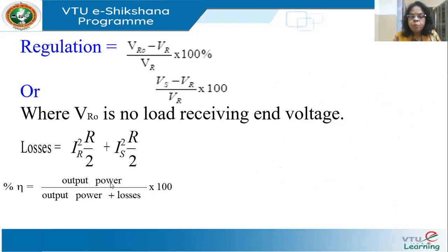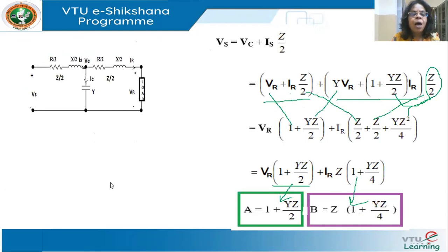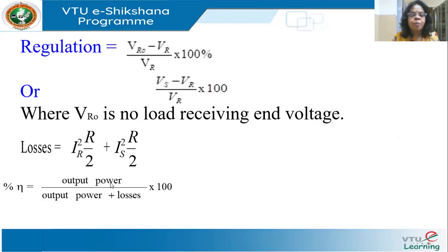Regulation can be defined in two ways. One is (no-load voltage minus full-load voltage) as a percentage of full-load voltage. The other is (sending end voltage on full load minus receiving end voltage) divided by receiving end voltage. The values differ slightly. For losses in the T model: the current in the right half is IR, so loss = IR²·(R/2); the current in the left half is IS, so additional loss = IS²·(R/2). Total loss = IR²·(R/2) + IS²·(R/2). Efficiency = output power / (output power + losses) × 100.